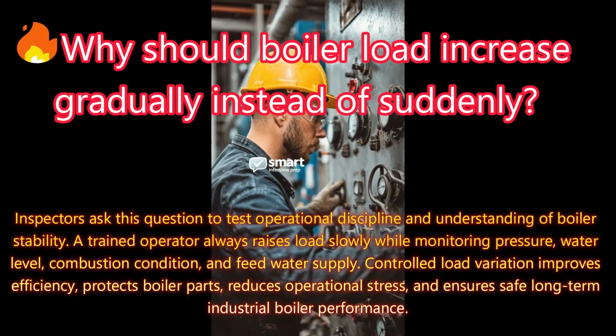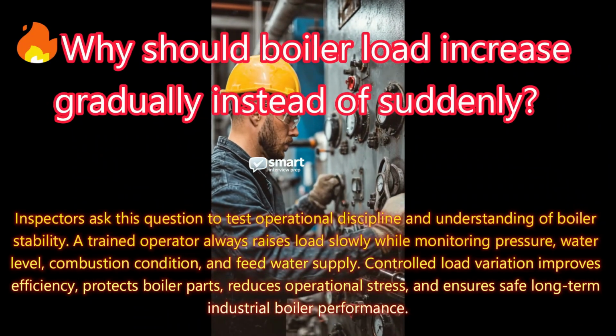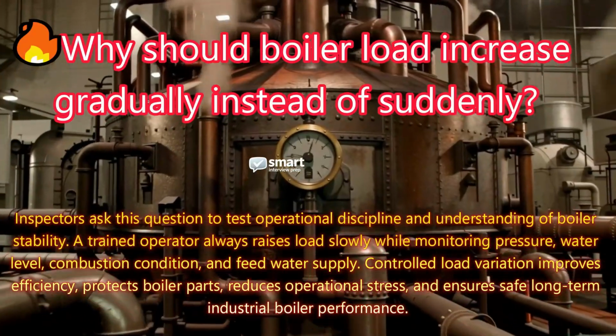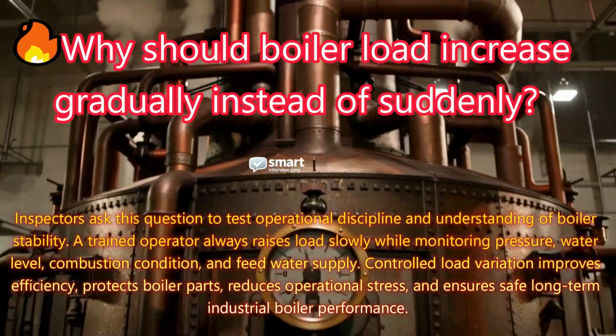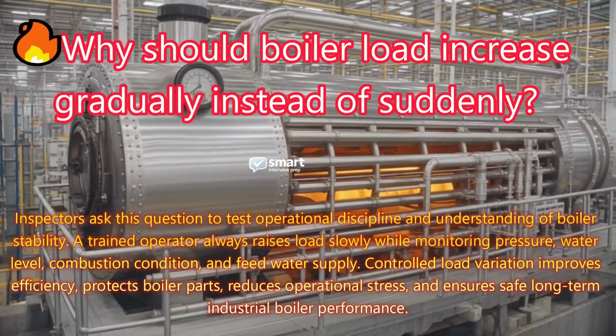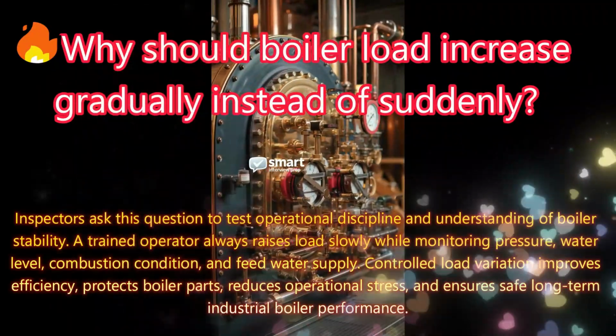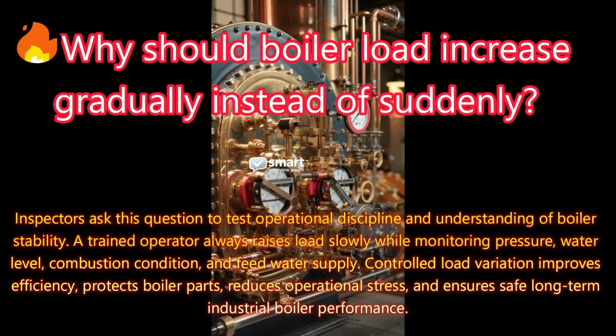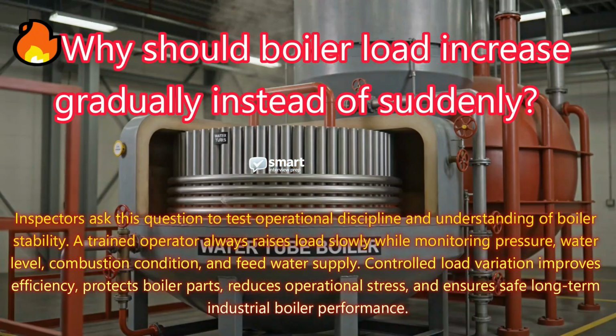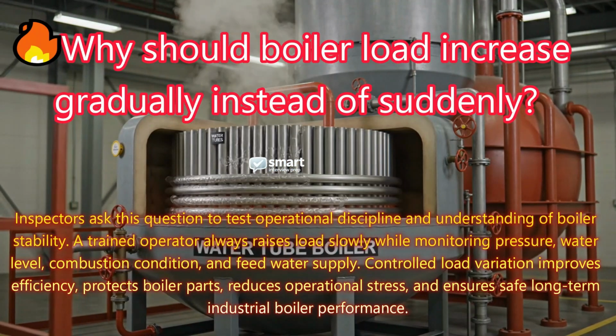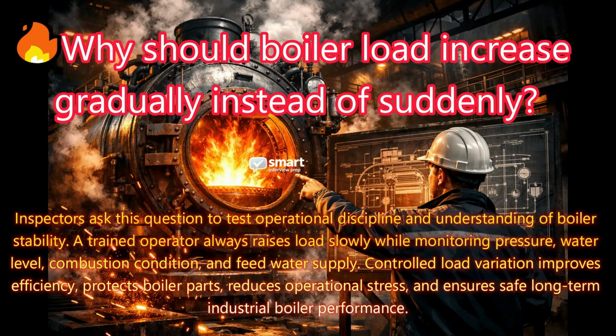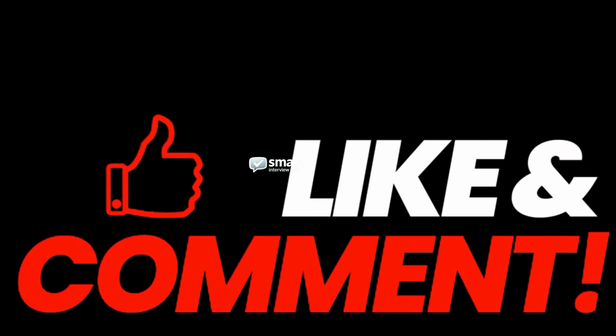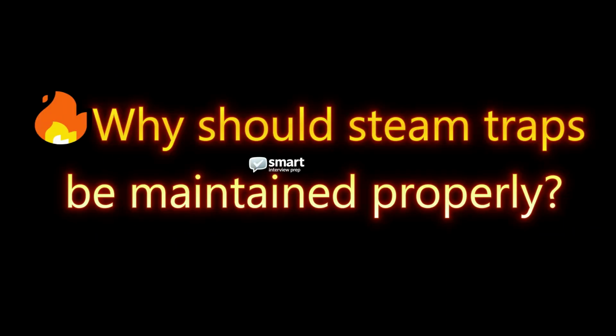Inspectors ask this question to test operational discipline and understanding of boiler stability. A trained operator always raises load slowly while monitoring pressure, water level, combustion condition, and feed water supply. Controlled load variation improves efficiency, protects boiler parts, reduces operational stress, and ensures safe long-term industrial boiler performance. Why should steam traps be maintained properly?